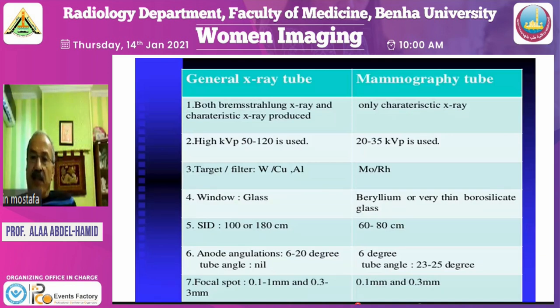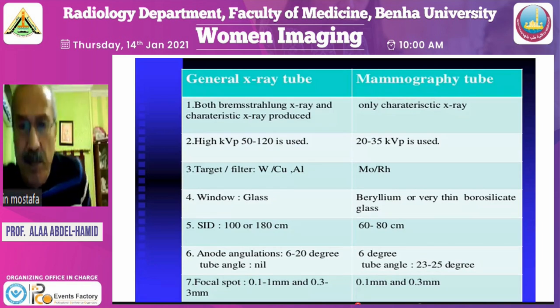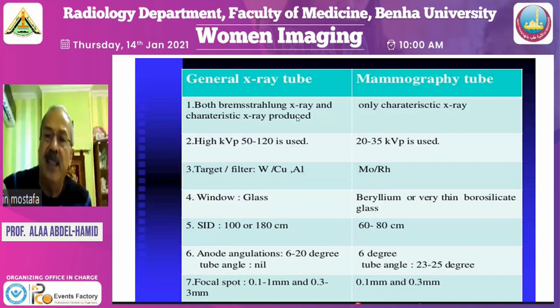We have so many differences between the general X-ray tube and the mammographic tube. The general X-ray tube uses both types of X-ray, the type which is not controlled and the characteristic X-ray beam, and the mammographic tube produces only characteristic X-ray beam. In the general X-ray tube, we use a high kilovolt technique between 50 to 120 kilovolt, but in mammography, we use 20 to 35 kilovolt. The target filter component is formed of either tungsten or copper in the general X-ray tube, but it is formed of molybdenum, and the filter here is formed by rhodium. The window in the general X-ray tube is formed of glass, but that of the mammographic machine is formed of beryllium or very thin borosilicate glass.